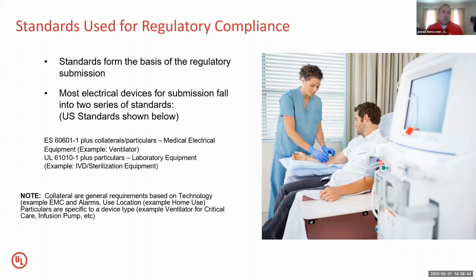When we talk about the devices that we would typically see around the COVID-19 situation, we really get into two basic electrical device standards that we see submitted on a regular basis. First is devices submitted that would fall under the standard ES 60601 plus its collaterals and particulars. This is a series of standards that provides everything from making sure your device doesn't cause electric shock to the user, electric shock to the patient, all the way down to looking at whether the device correctly reads the amount of CO2 that the patient exhales during use of a ventilator, or whether there's an SpO2 sensor, how well that device will actually measure the oxygen saturation in the blood.